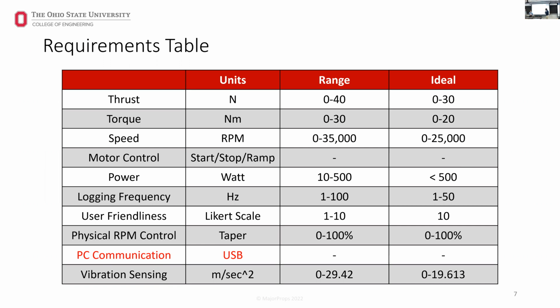So they have to spec based on this range, because usually the nominal value is not what you actually see. Okay, so basically you have to go back to the motor selection and make sure that one is checked. Then the torque also must be provided, so basically your end range is where you'll be safe.